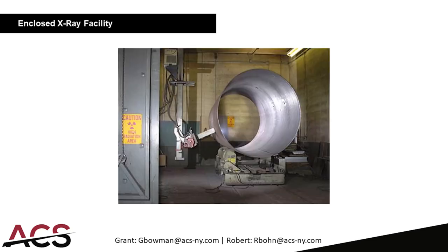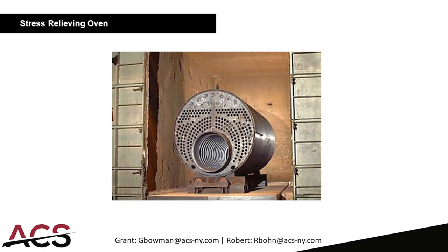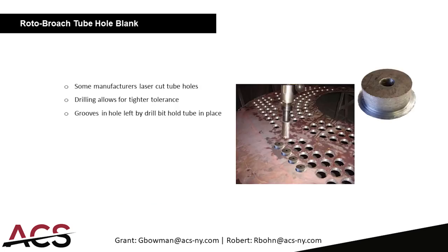The boiler manufacturer has an enclosed X-ray facility where they X-ray the welds to check for integrity before moving on in production. There is also a stress-relieving oven where the boiler is baked for a time period to relieve all the stresses in the metal. The tube sheet is drilled — some manufacturers laser cut, but others drill because it allows for a tighter tolerance. The grooves left by the drill bit allow the tube hole to hold the tube in place.